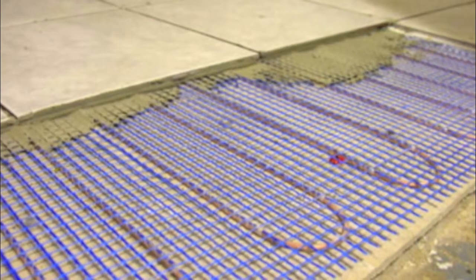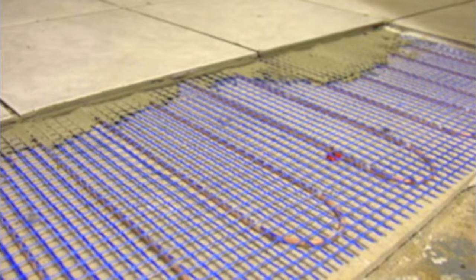That's right. It's a hydronic radiant heat, which means there are water pipes from the boiler under the floor. We did that because otherwise we would have had to use those toe kick heaters which had fans, which would be noisy, which we didn't want. And it's such a large area with no wall space, so you couldn't have baseboards. So it really made sense for us. My understanding too is it's a lot more energy efficient. It's very efficient. The water isn't nearly as hot as the water that runs through baseboard. It's closer to 100 degrees instead of 180 degrees.